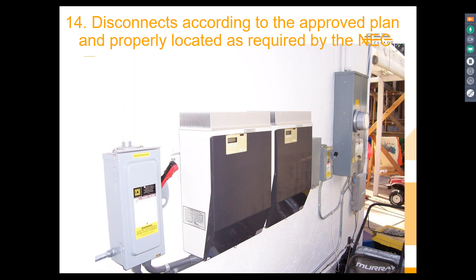Now, in general, Article 690 requires us to have the switch for disconnecting equipment to be within sight of the equipment. So there's our DC disconnect there. Unfortunately, the AC disconnect on this particular system was on the outside of the house. This is in a utility room on the other side of the wall, but I can't see that switch from there. So if I'm working on this inverter, I would have to go outside and open that switch.